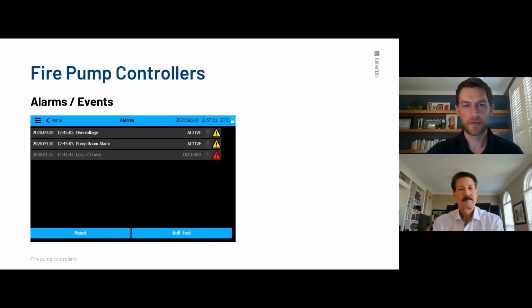But that's just the drop-down menu, and now we'll start looking at each one of these individually. So this is the alarm page. The drop-down menu to that alarm bell will send you here. Like I said, this is if you have any active alarms or if you've had any major alarms. We classify our alarms in 2 separate ways. There's the yellow ones that are, I guess you'd call them basically the FYI alarms. They're important alarms to look at, but they're not the critical ones. So they're put as yellows.